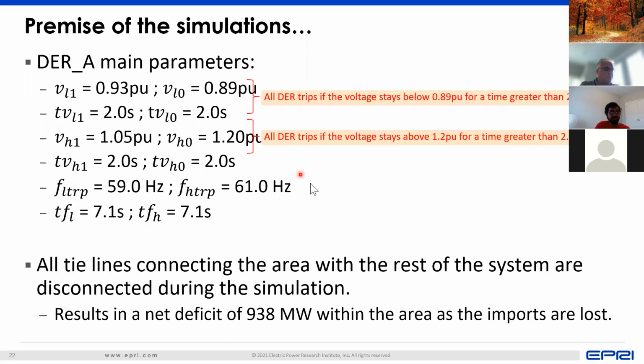So we have our DERA model, which says that all the DER would trip if the voltage goes below 0.89 per unit for 2 seconds, and it would trip if the voltage goes above 1.2 per unit for 2 seconds. So the goal is that if this entire area disconnects from the rest of the system, can this area continue to survive and operate in a stable manner with this DER present? And the reason it's important to do these studies from a planning criteria is because supposing there is an extreme event that requires this area to be disconnected. Let's say there's a tornado that goes through that region and really causes those transmission lines to trip. Then we need to understand if that remaining area can survive.